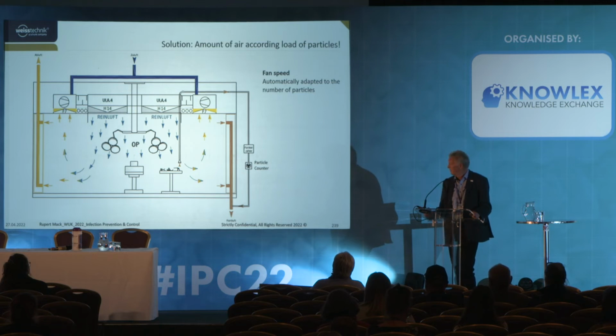So it's not done yet, but it could easily be done technically. You have a section where you measure the number of particles, and you can show whether it's good or not good. If it's not good, you can speed up the air volume in order to wash out the unwanted substances as quickly as possible. UCV canopies like this work in such a way that there's a certain amount of fresh air and a certain amount of additional recirculating air. As long as we bring it in via HEPA filters, there's nothing against it.